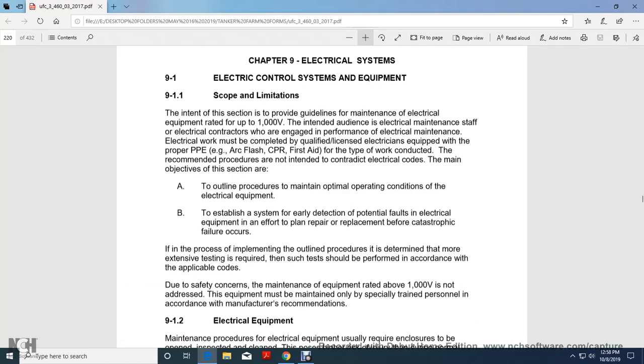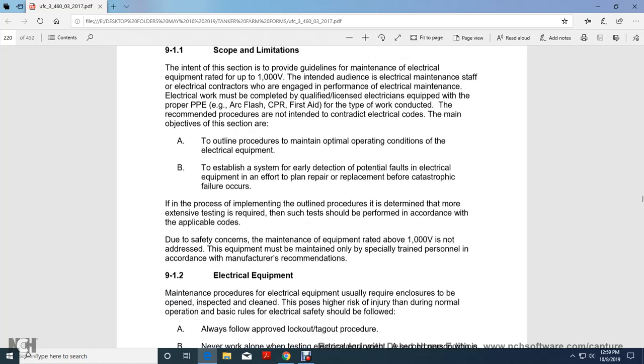9.1. Electrical control systems. The scope and intent of this section is to provide guidance for electrical equipment rated up to 1,000 volts. The intended audience is electrical maintenance staff and electrical contractors engaged in the performance of electrical maintenance. Electrical work must be completed by qualified, licensed electricians equipped with personal protective equipment for the type of work conducted. The recommended procedures are not intended to contradict electrical codes. The main objectives of this section are to outline procedures to maintain optimal operating conditions of electrical equipment and to establish a system for early detection of potential faults in electrical equipment, in an effort to plan repair or replacement before catastrophic failures occur.